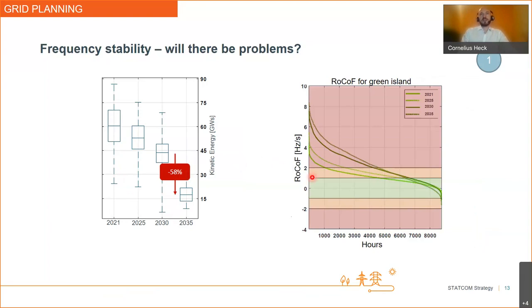So far, we know that 1 hertz per second RoCoF would be fine and should be survived. 2 hertz per second could be critical, but could also be survived. And everything above the 2 hertz per second limit will most likely lead to a large blackout of greater parts of Europe. And what you can see here is the RoCoF on the y-axis and the hours of the year on the x-axis. And you can see the lines for the different scenarios here, so 2021 up to 2035.